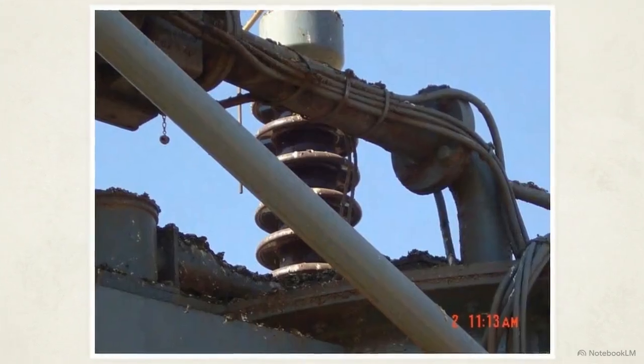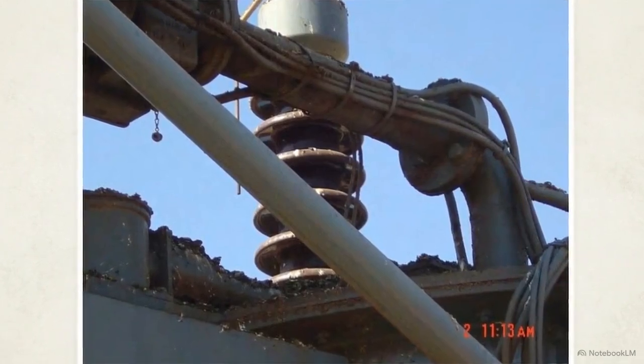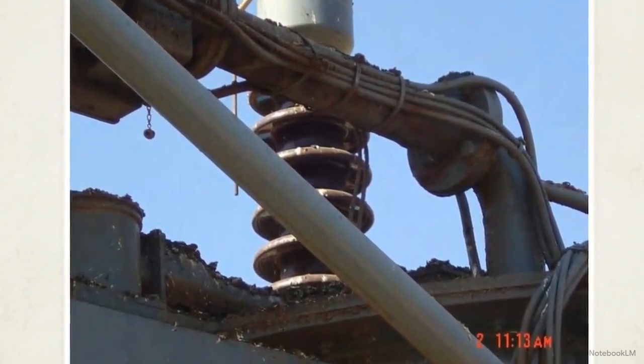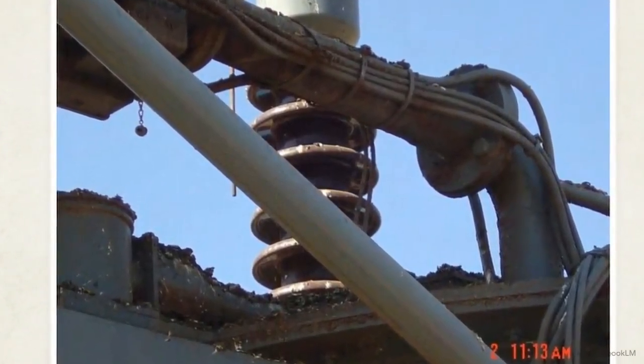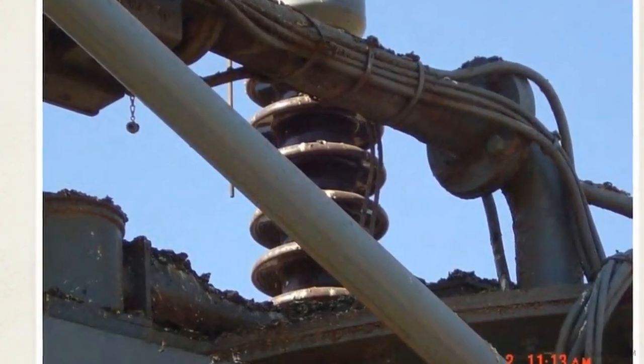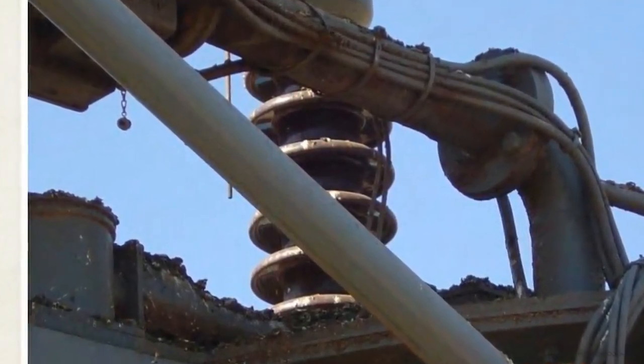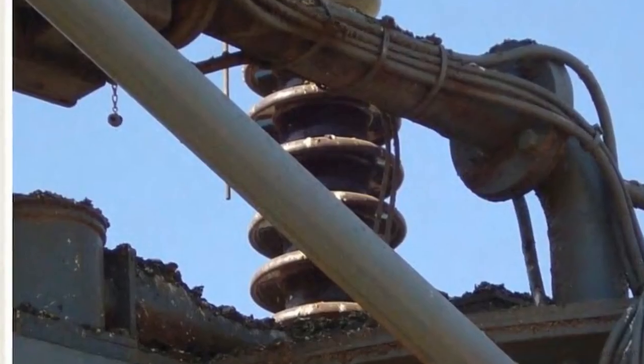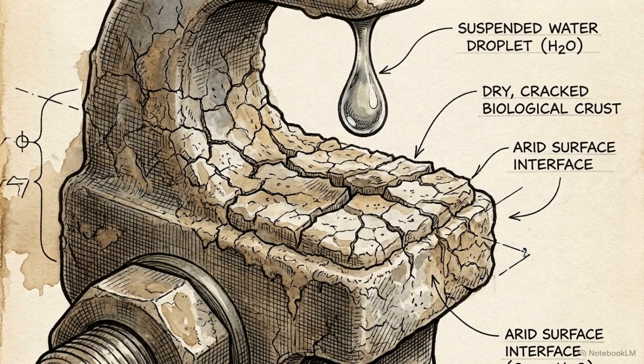But biology still finds a workaround, leading to a failure known as guano pollution flashover. This field photograph captures the buildup. Over long, dry seasons, birds roost on the towers directly above the hardware, depositing feces until a thick layer of guano completely covers the ridges of the electrical insulators. As long as the weather stays dry, the system holds. The environmental trigger is moisture.